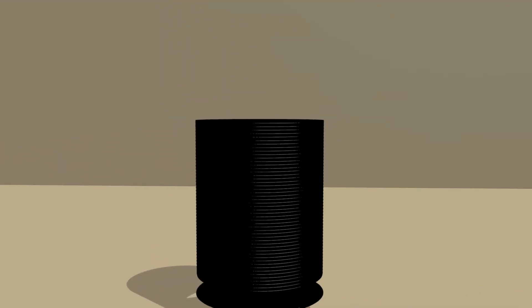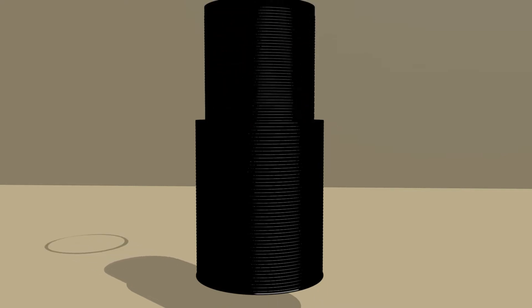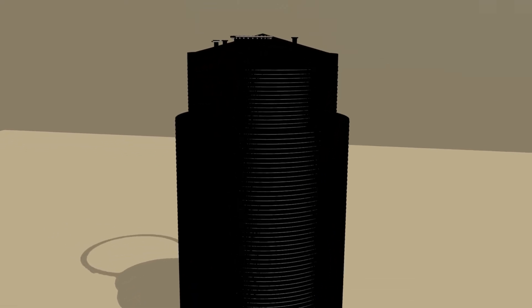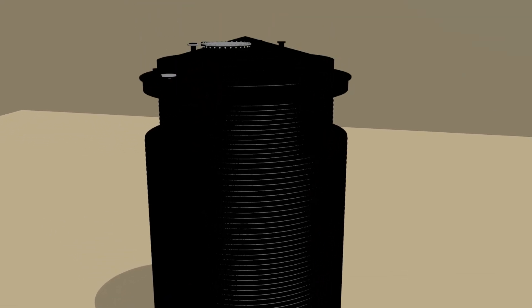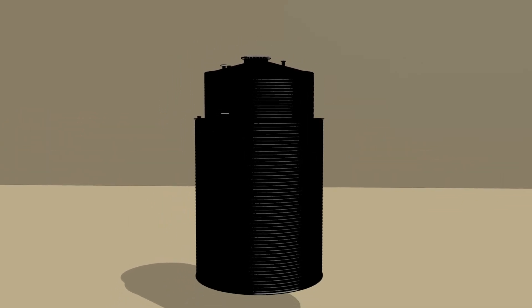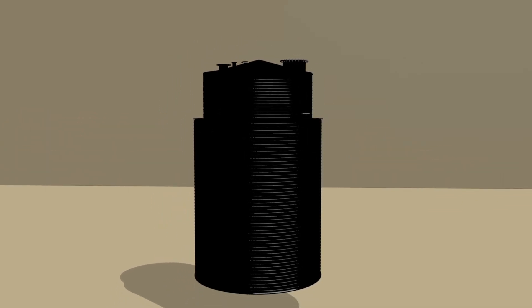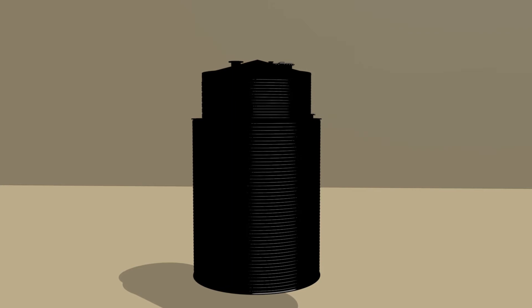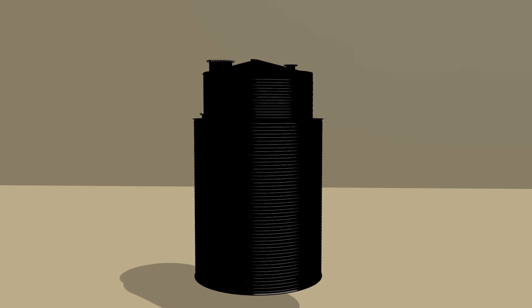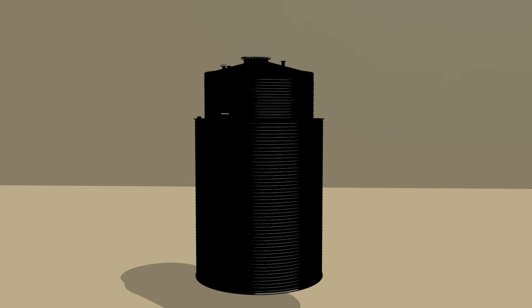Integrally bunded storage tanks can be manufactured, with the storage tank being positioned inside a larger diameter vessel. A rain skirt is added to prevent the ingress of rainwater. The outer bund has its own base and is structurally independent from the inner containment tank and acts as a containment should there be any unintended escape of liquid, such as an overfill.